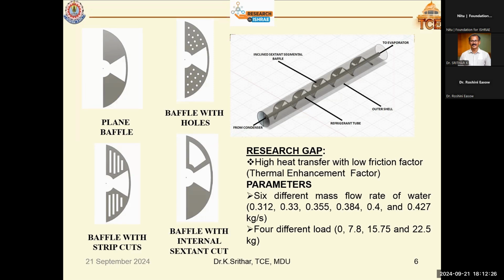There are 4 types of inserts. These inserts are designed to have a very high heat transfer rate. At the same time, they have very low friction, thereby low pressure drop. So pressure drop should be low, and at the same time heat transfer rate should be high. This can be measured by a parameter we call the thermal enhancement factor. This is a direct measure of the ratio between heat transfer and friction. So based on that, we designed 4 inserts, and the 4 inserts are connected in a continuous arrangement like this. So that is a diagram of how it is fitted inside the condenser.